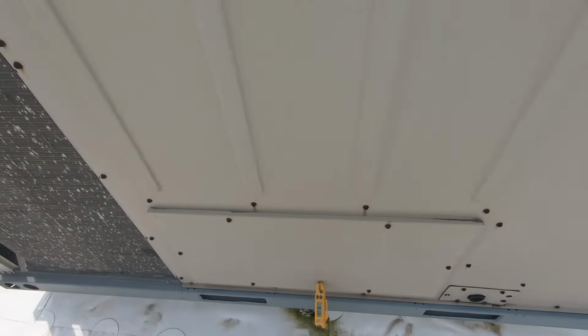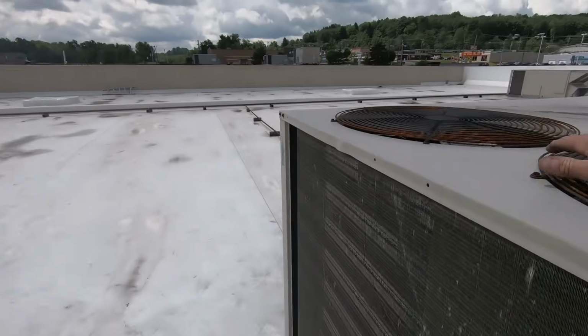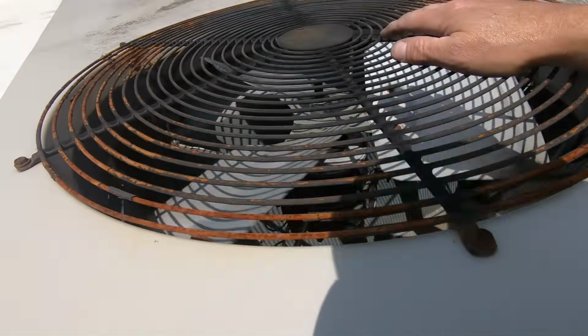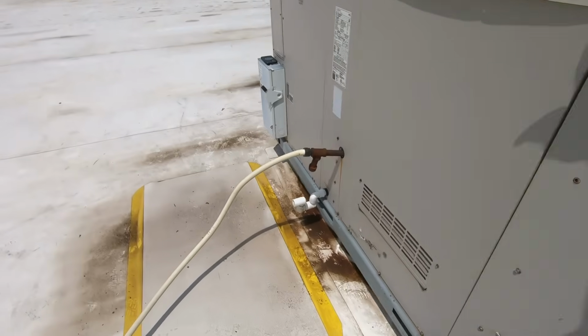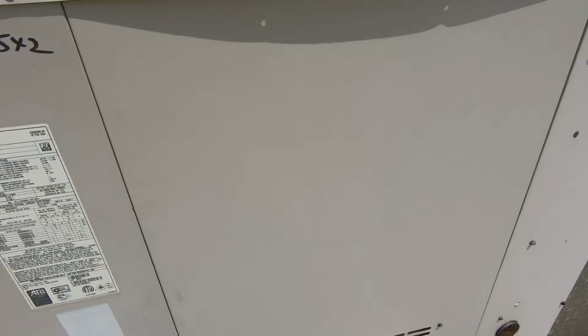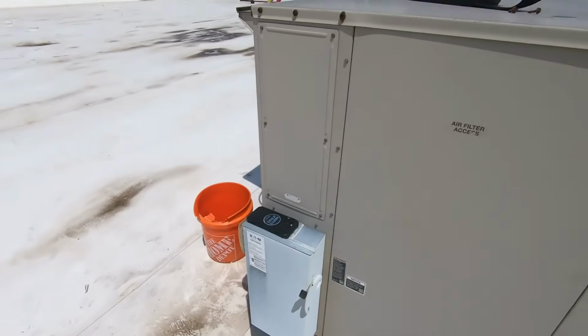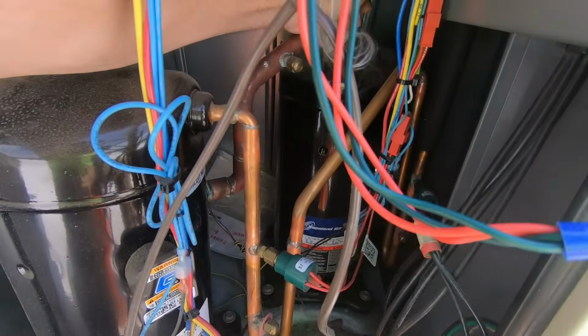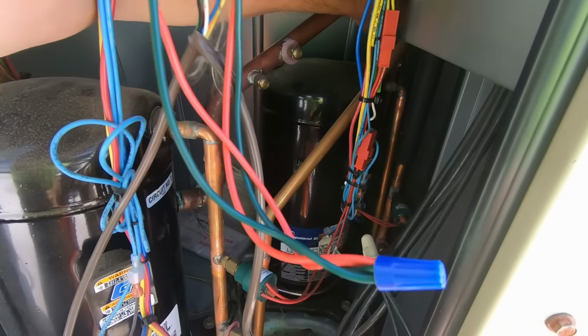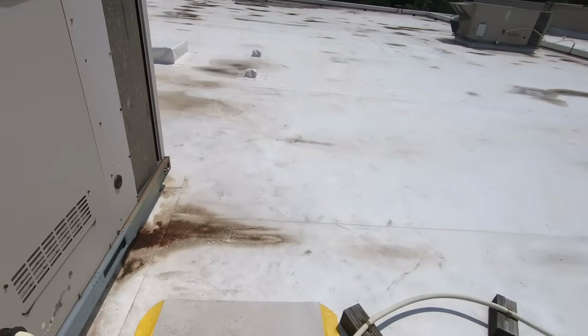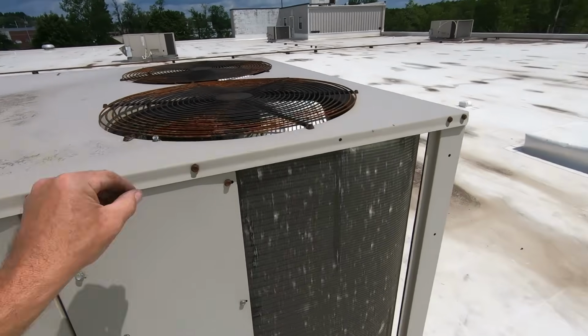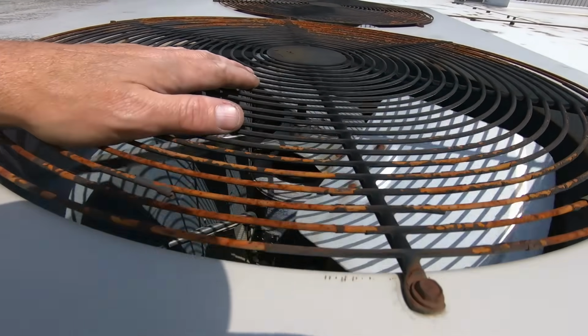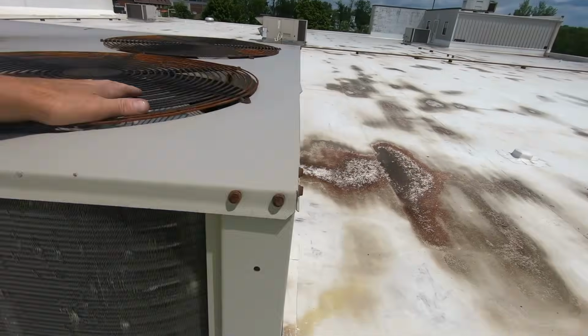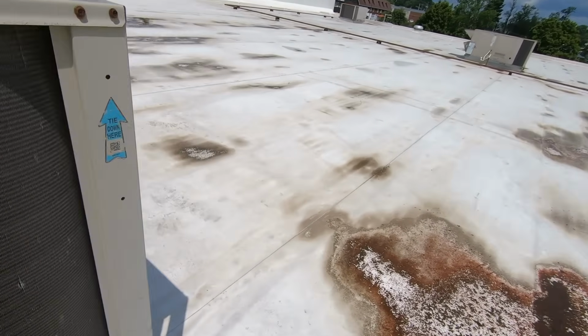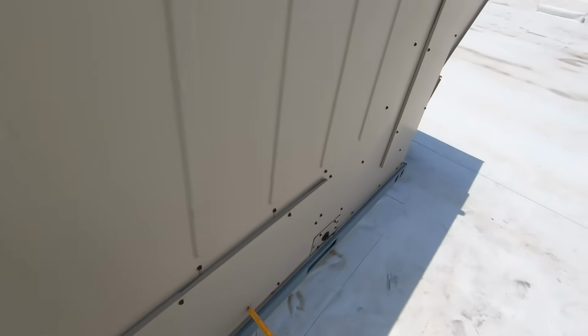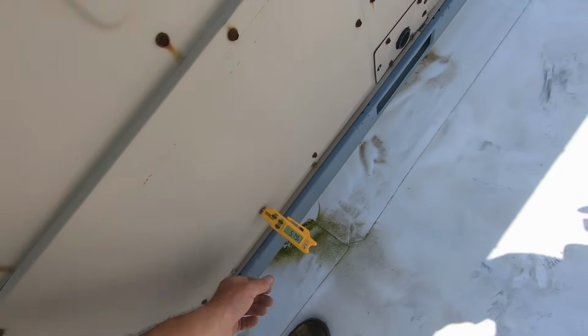Let's check some supply air temps. This fan has not kicked on. Wires are connected. Let's give it a minute. Blower is running. Oh yeah. Suction line is cold. This guy's not running. Running backwards. I'll dig into that. This one's gonna get the same treatment as the rest though. Coil cleaning. We're at 58 and dropping.